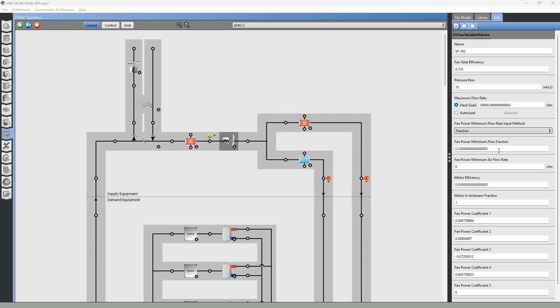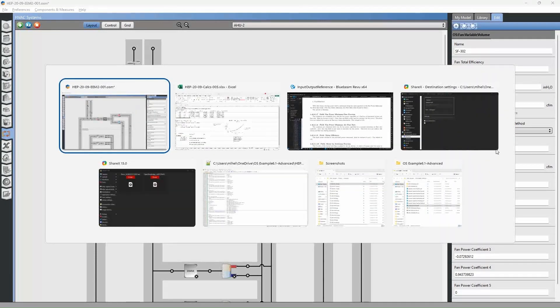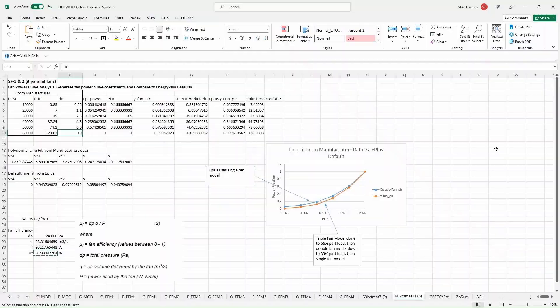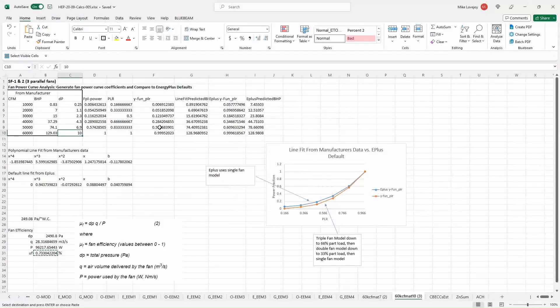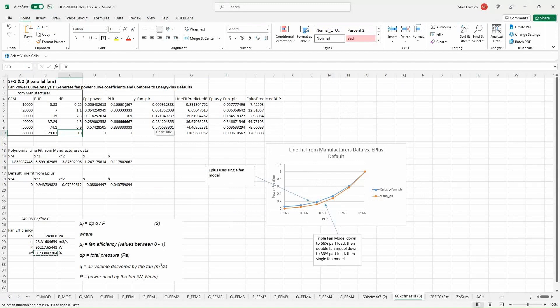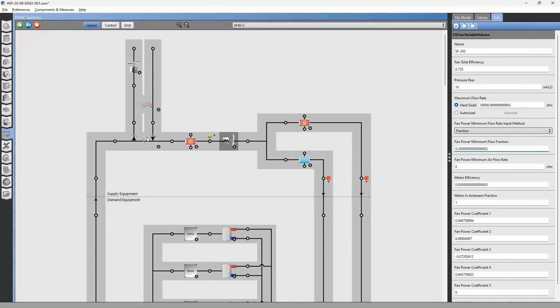So for most fans, you can go down to about 30% speed for a single fan. But when you have these parallel fans, you can go down to a much lower speed or a much lower volumetric flow rate. And in this instance, our lowest part load ratio, our lowest flow rate is 0.167. We're going to change this to 0.167.